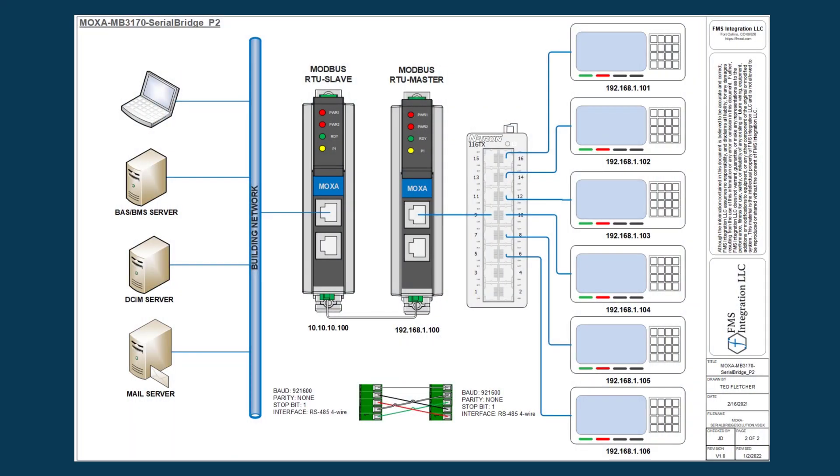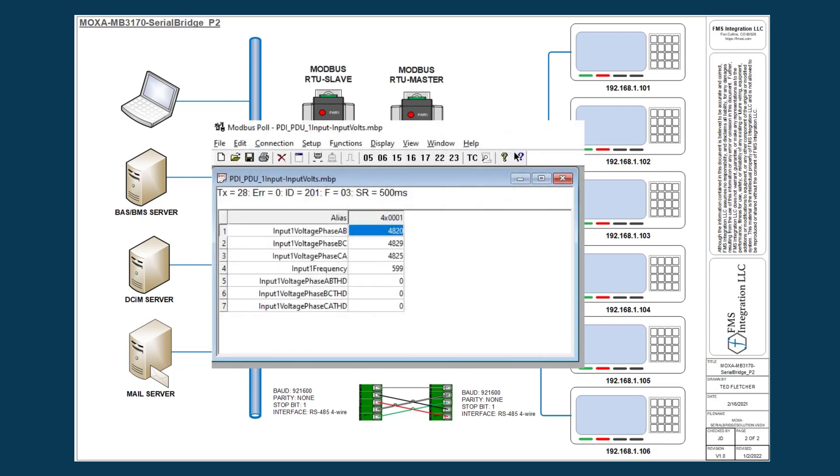Once everything's been programmed and cabled up, then it's a matter of updating your master systems for using that new mapping. And then if not using one of the master systems, use a third party tool such as Modbus poll or Modbus tools to go through and scan the devices just to ensure there are no comm issues.